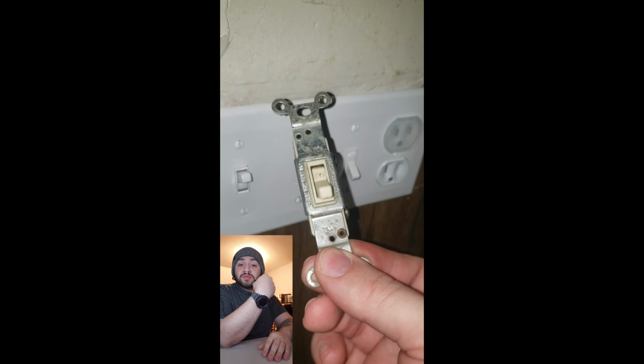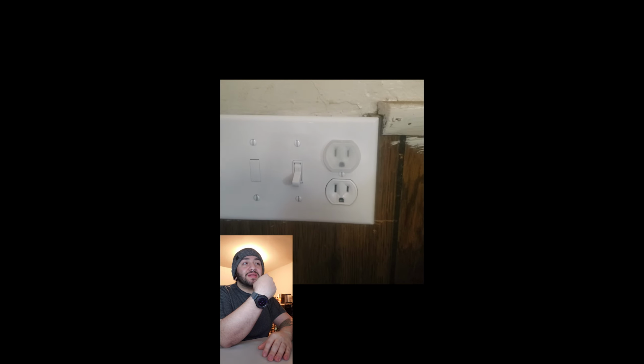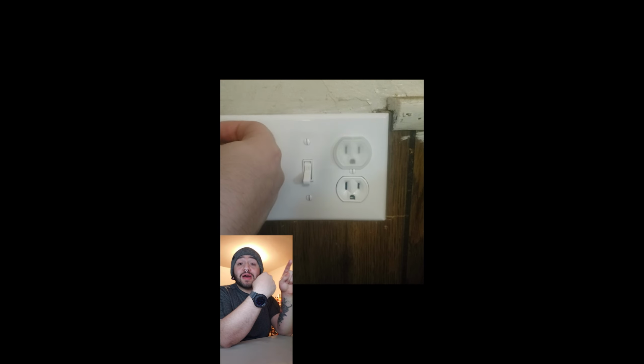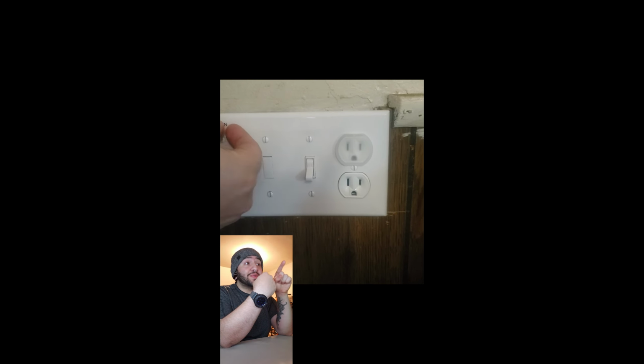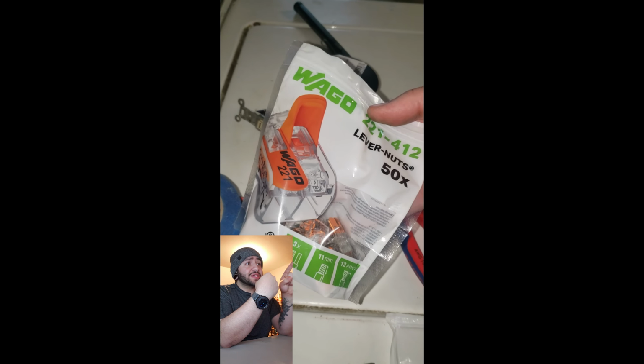And after everything was put back on, she's like, hey, can you switch that for the new light switch? Because it would look better with a new switch. I said, I told you. But when I was changing that one, the knob and tube old copper snapped. And so I had to Wago in some 14 gauge solid to make that connection.